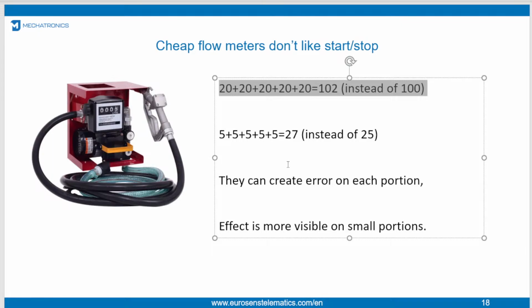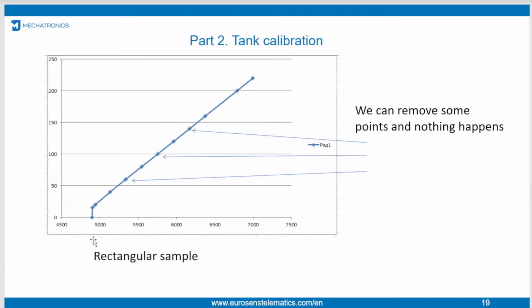But do we need a lot of calibration points at all? For example, we have a rectangular tank. Its calibration chart will look like that. It's a straight line between empty and full tank. So what happens if we have only 2 points, empty and full? To calculate any value in between, the sensor will look up a value lying on the same straight line. So it makes no difference how many calibration points you take for a rectangular tank.